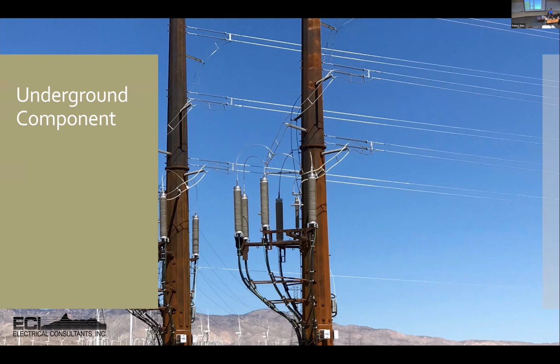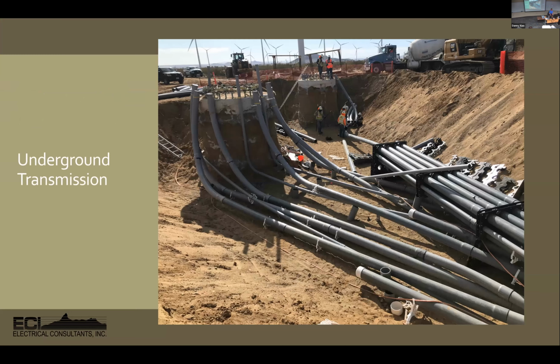This was very challenging for the project, as can be seen by all of the underground cables. When you bury a circuit, there's a lot of thermal heating that occurs, and the earth acts like an insulator. So whether we're using copper or aluminum, the material itself, if it gets too hot, will change properties—copper will melt at some point. Melting probably won't occur at normal operation, but it can anneal and begin to change a little bit under the earth. So we don't want the conductor to get overly hot.